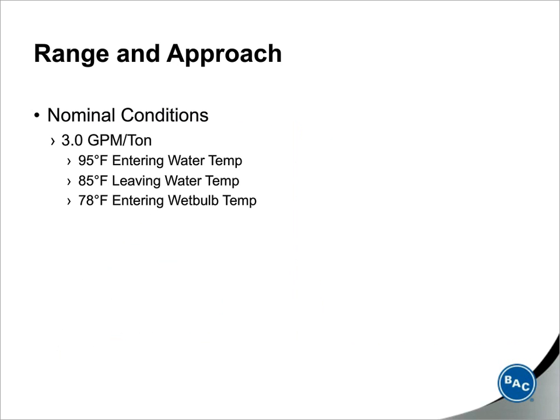So nominal design conditions for the condenser water loop in general: 95 degrees back into the cooling tower, and back to the condenser or chiller, 85 degrees leaving the tower and going to the chiller, and a 78-degree outdoor ambient wet bulb temperature. So these are very typical conditions for many regions in the U.S., and that includes the Northeast. Again, it's 95 into the tower, 85 out of the tower, 78-degree wet bulb.